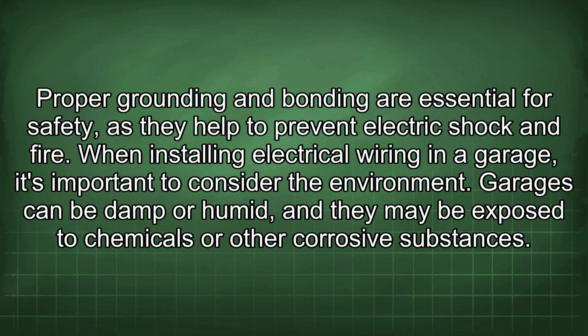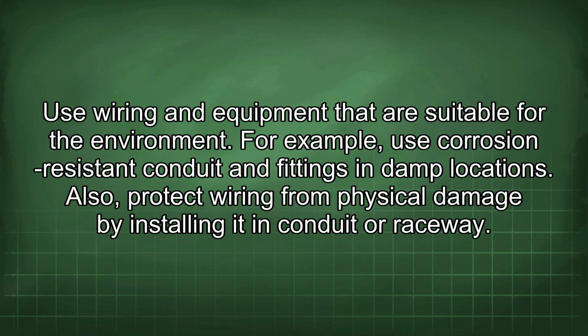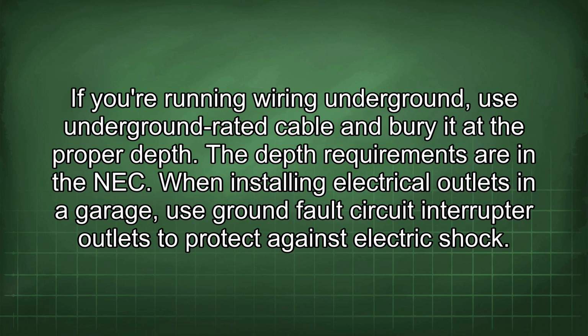When installing electrical wiring in a garage, it's important to consider the environment. Garages can be damp or humid, and they may be exposed to chemicals or other corrosive substances. Use wiring and equipment that are suitable for the environment. For example, use corrosion-resistant conduit and fittings in damp locations. Also, protect wiring from physical damage by installing it in conduit or raceway. If you're running wiring underground, use underground rated cable and bury it at the proper depth. The depth requirements are in the NEC.